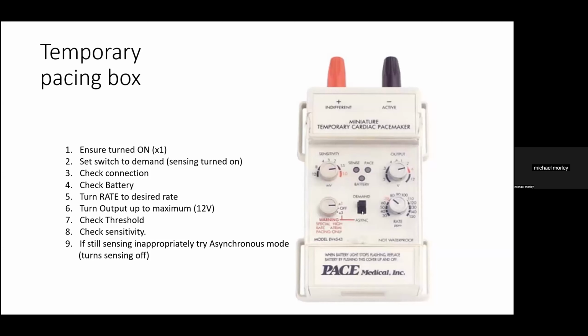So demand is that it will sense as well as pace, and that's the two fundamental functions of a pacemaker: the ability to send impulses down to stimulate the heart to beat, but also to be able to sense intrinsic activity, and with demand pacing only to pace when necessary. That is, when there's no intrinsic activity or when the heart rate drops below a certain level.